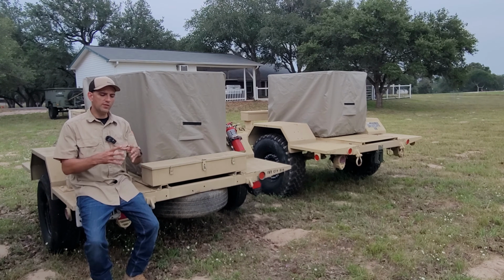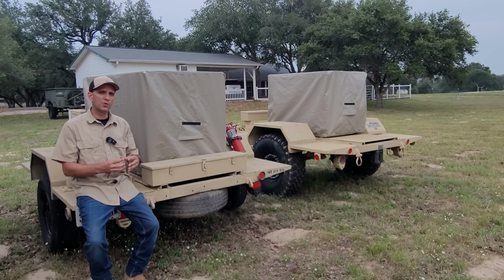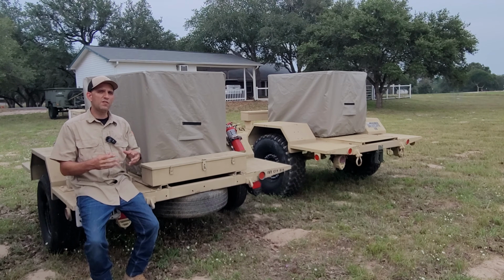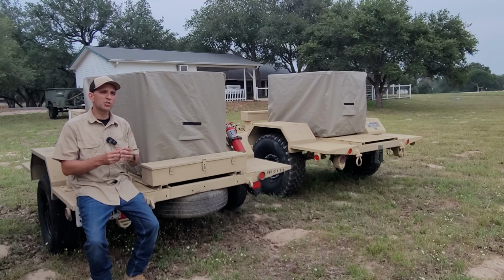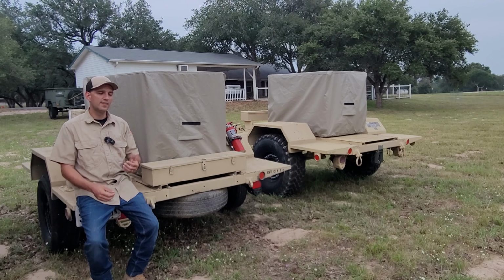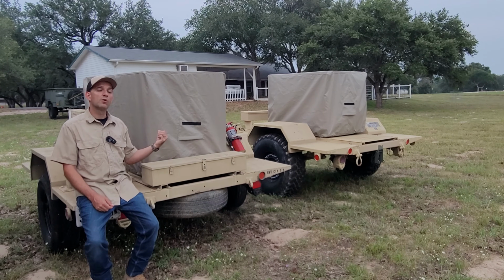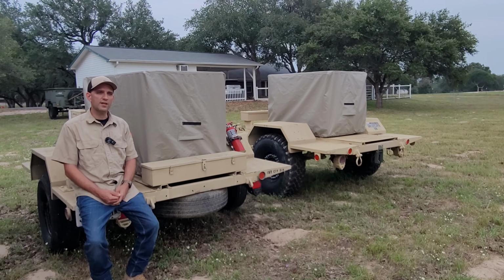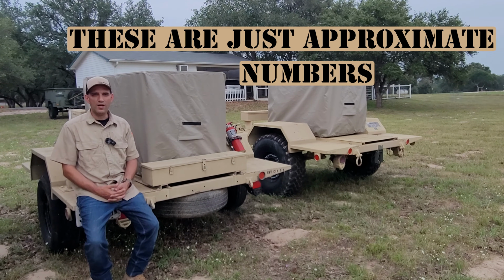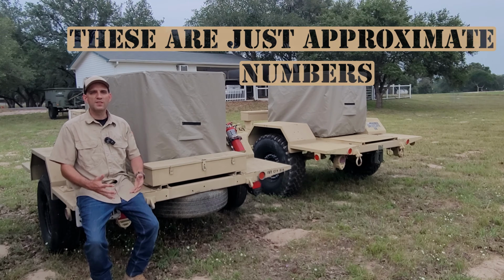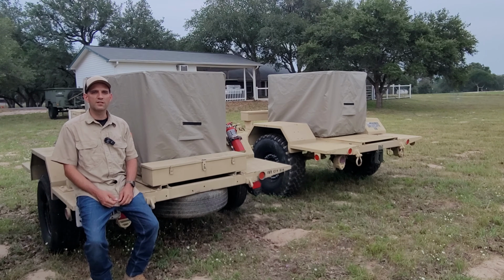What the overload fault is for is if it detects overcurrent that's just a little bit too much overcurrent for too much time, that's gonna then damage, because it's gonna create too much heat in the generator head. So say if you were running like 13,000 watts for 5 or 10 minutes and it starts generating a little bit too much heat, then it will cause it to trip. But if all of a sudden you jam 15,000 watts on there and close the contactor, it's just gonna bog the engine right down.